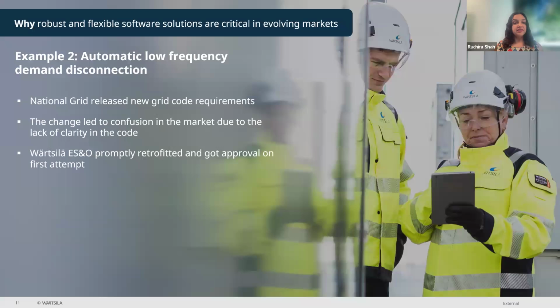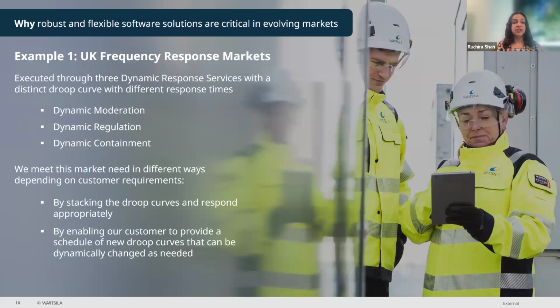Another way that we've met this need is by stacking the droop curve and responding appropriately. One thing we've noted is that as these markets move towards energy storage, we see issues cropping up that the market services are not always initially clued into. So, one thing with batteries is that obviously they can respond to these frequency changes very quickly, and that's usually a key attribute of batteries.